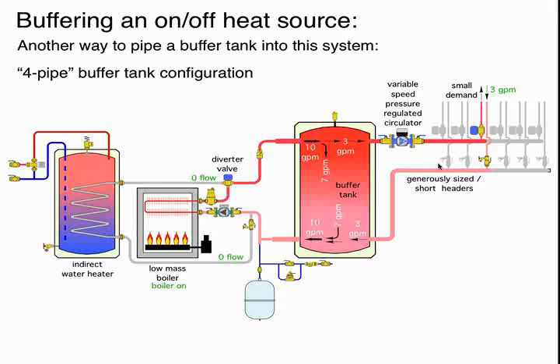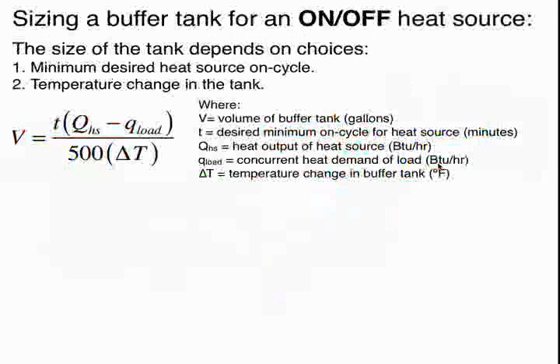But again, we would have slightly higher flow velocities in the upper and lower portion of that tank and perhaps get a little more mixing compared to the 2-pipe. If you want to calculate the size of a buffer tank, we need to know a few things.